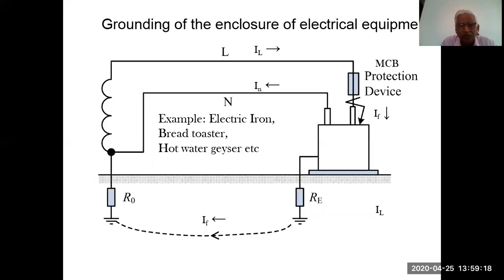Now you can see this one, grounding of an enclosure of electrical equipment. On the left side you see a transformer. The line is coming to a box, and the ground wire and the neutral wire are also coming to it. Assume that it is just like an electrical iron, bread toaster or hot water geyser. The transformer neutral is connected to the ground. The connection has a resistance, which I'm assuming to be R0. It is not a connected resistor; it is the conductor I have given, and I have assumed its resistance to be R0.